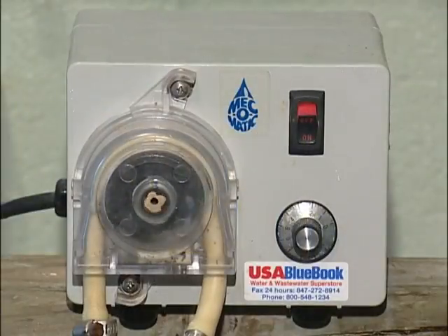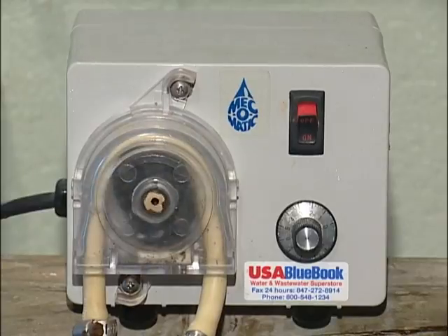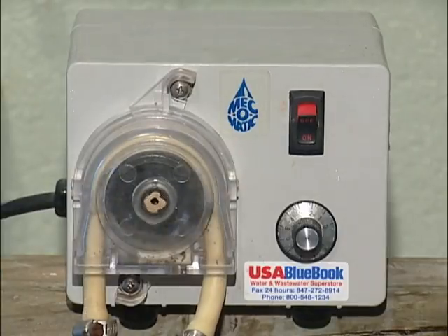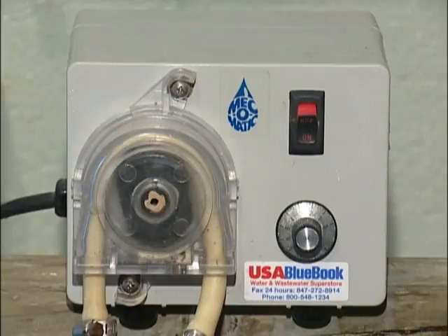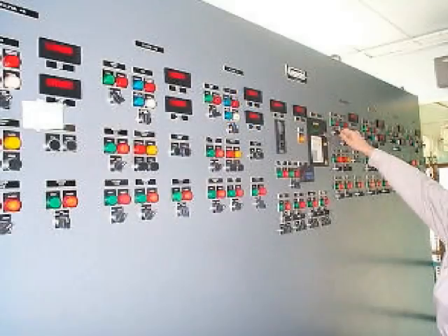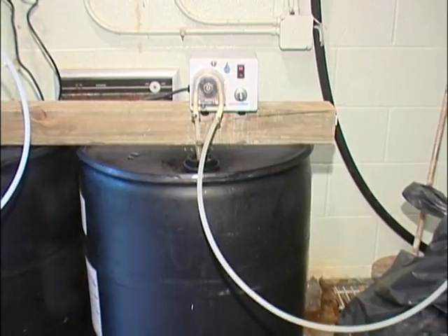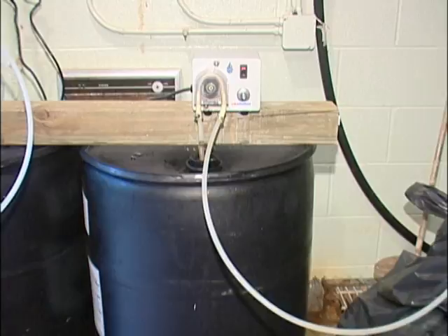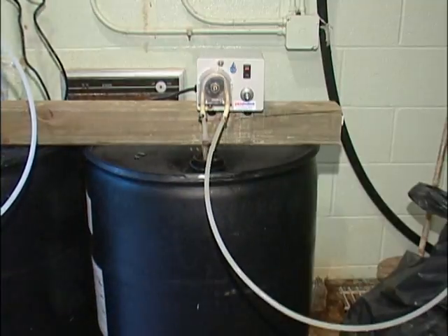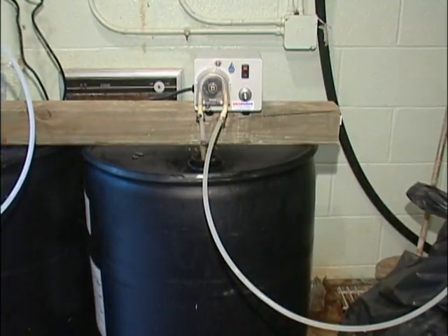Peristaltic pumps use a pliable tube and a rotating cam. As the cam presses against the flexible tube, it squeezes out the chemical in the tube. The feed rate can be adjusted by changing the speed of the rotating cam. Some pumps can be adjusted by setting an on-off timer for intermittent feeds. The pump will come on and feed for a preset time, then be off for a designated period of time.